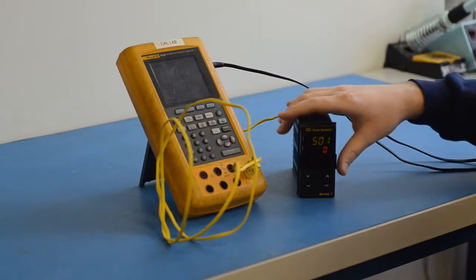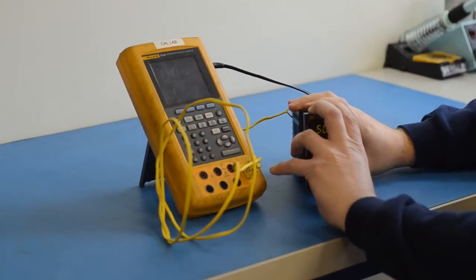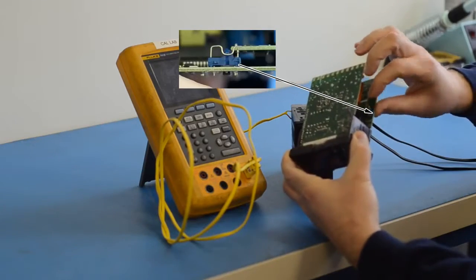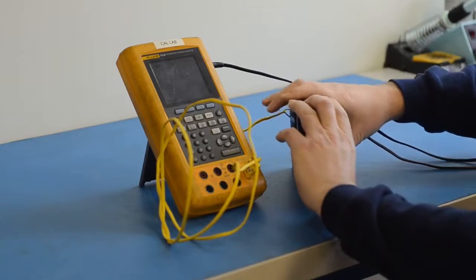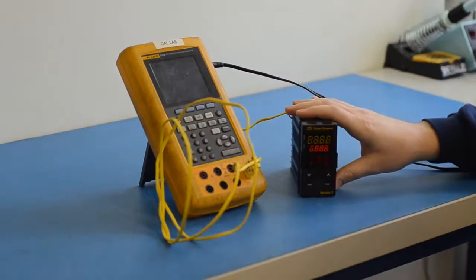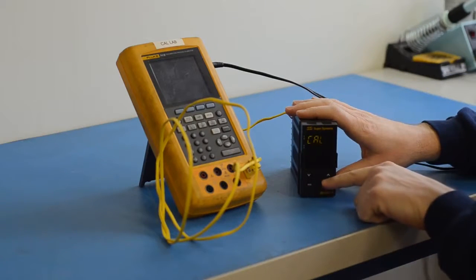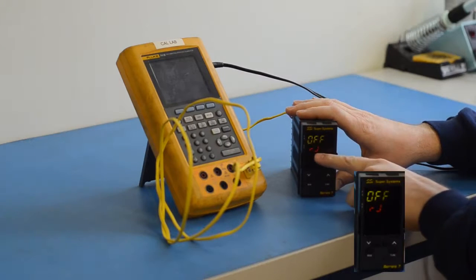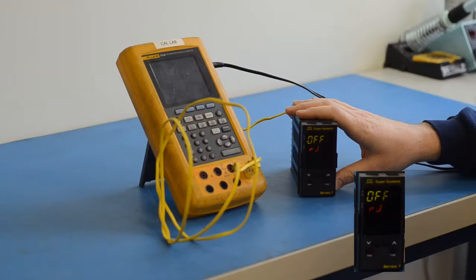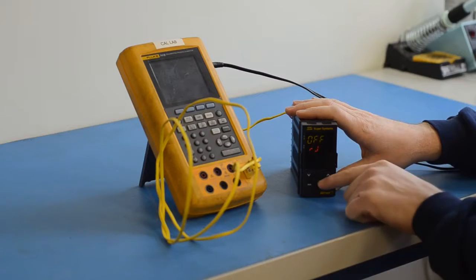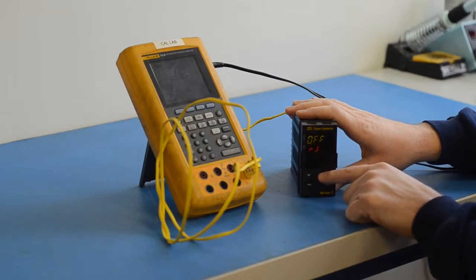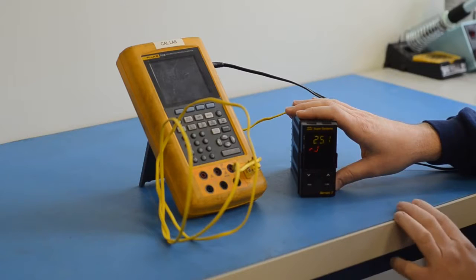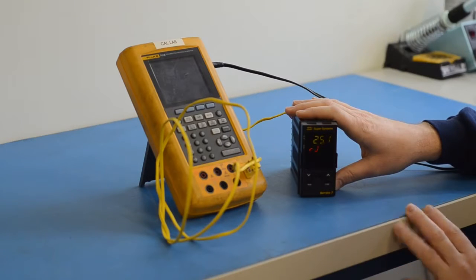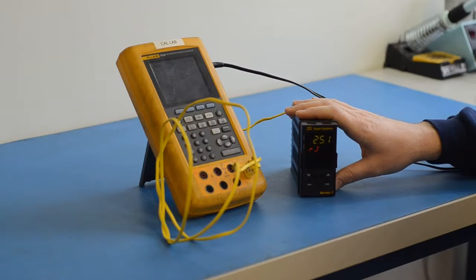So to make this adjustment, you will need to remove the instrument from the case, unlatch our jumper again for calibration mode, insert it back into the case, and now we're going to press the function button until we see the display shows RJ and it has the value of off on the top. We are then going to change, using the arrow buttons, the off, and it now gives us a value of 25.1. This value is a base value that it starts at in degrees Celsius.